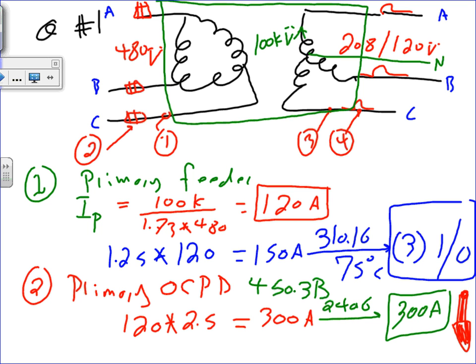The reason why I will always say, guys, you always use primary and secondary, is because most of the time we use a transformer like this to get us what? To get us a 208/120, and that we dump it into where? Into a panel. And guess what's going to be inside the panel, right at the top of the panel? A circuit breaker. So most of the time, really, you're going to have primary and secondary protection.